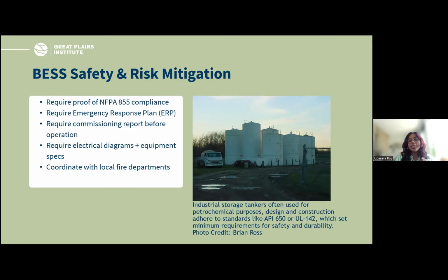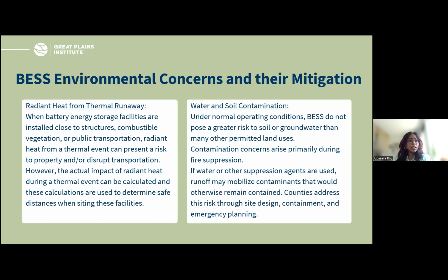That's one of the things we have to continuously remind ourselves: there are codes and compliances these systems need to have, a benchmark they have to meet. But it's the communities who have to deal with the risk, if and when that happens, and what to do. That's where NFPA does a really good job laying out an emergency response plan, having a lock box, having a good distance from racks, and a coordinated training plan for local fire departments. There are other safety concerns that come from the risks associated with BESS.